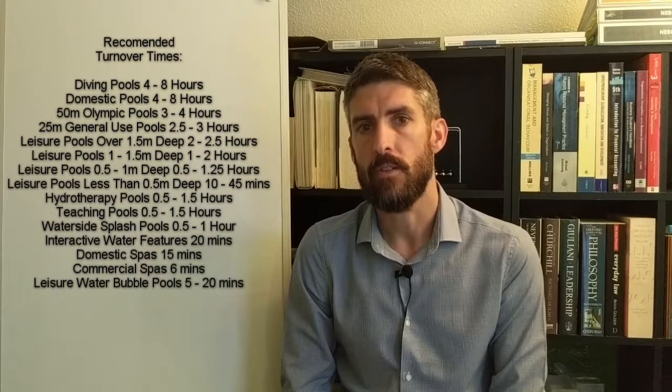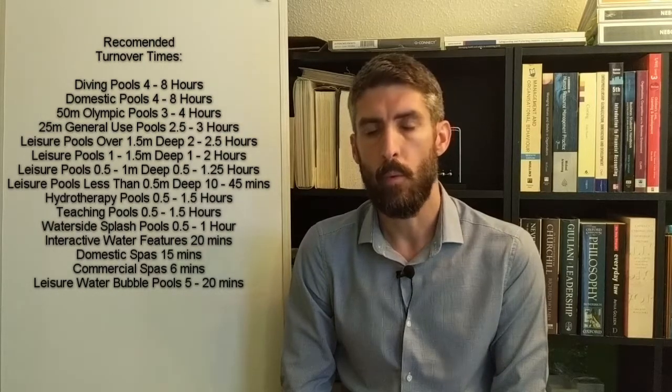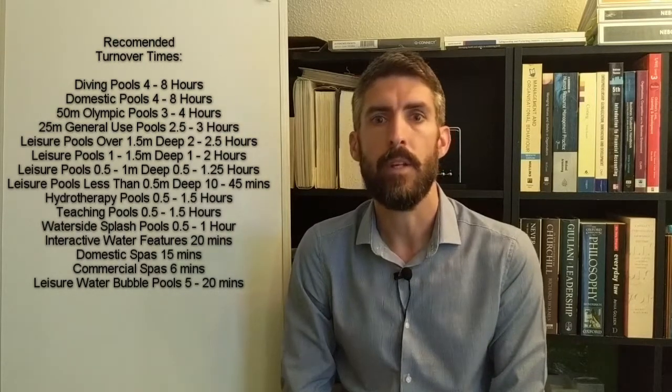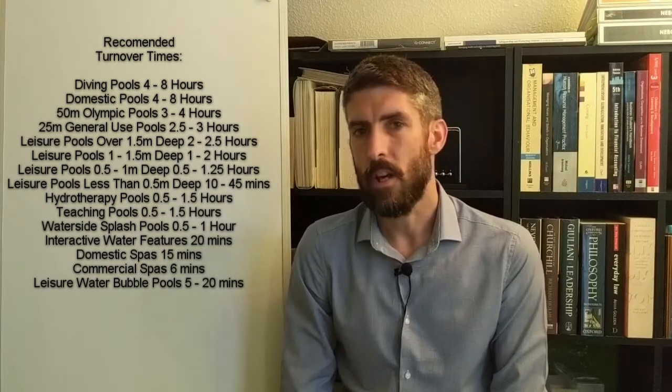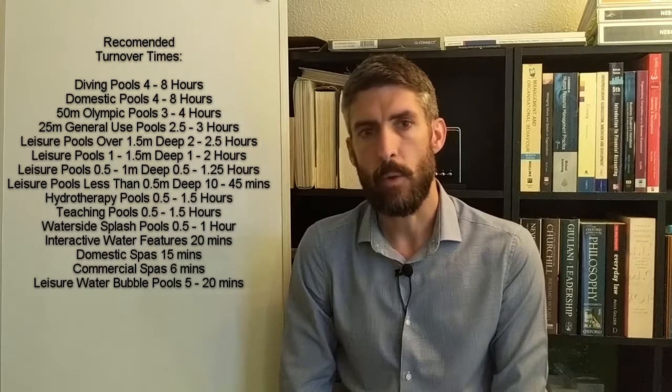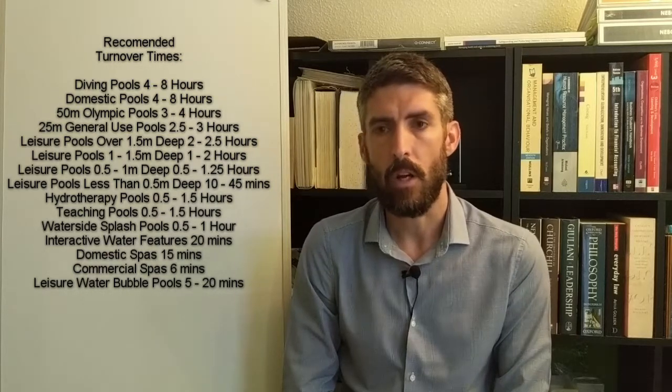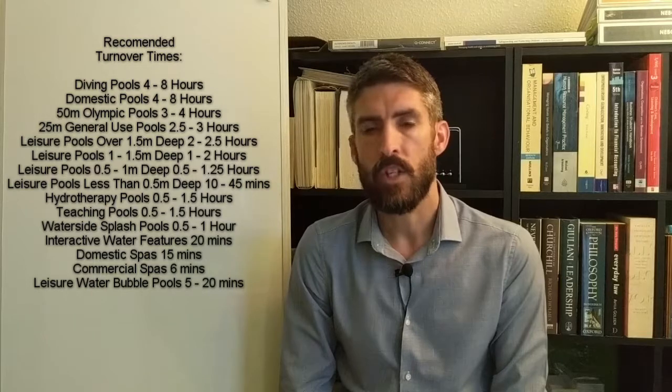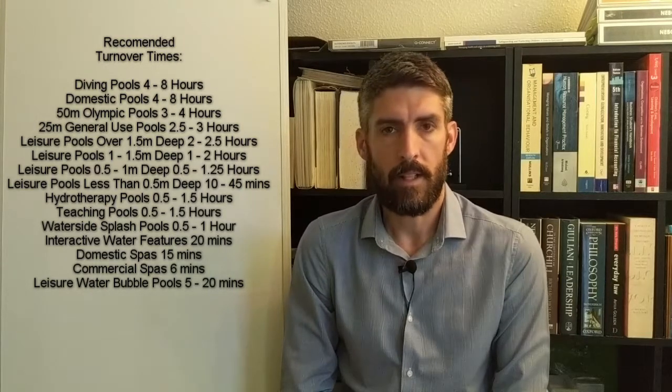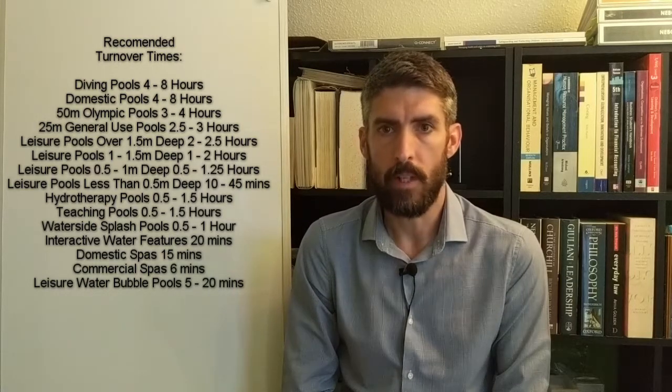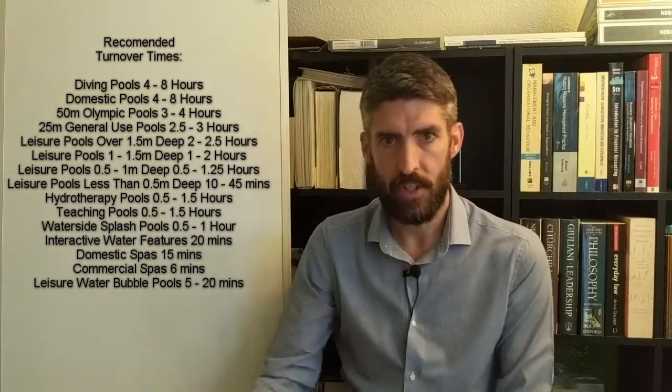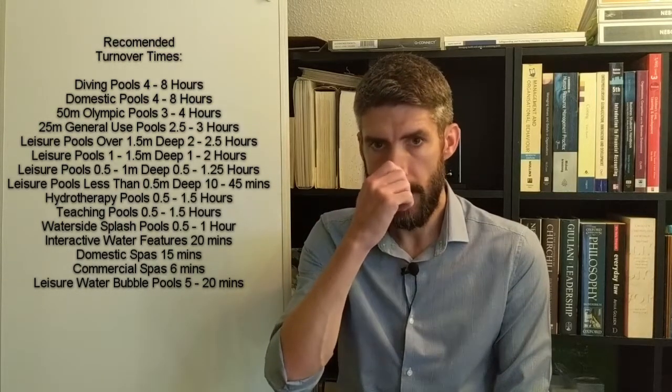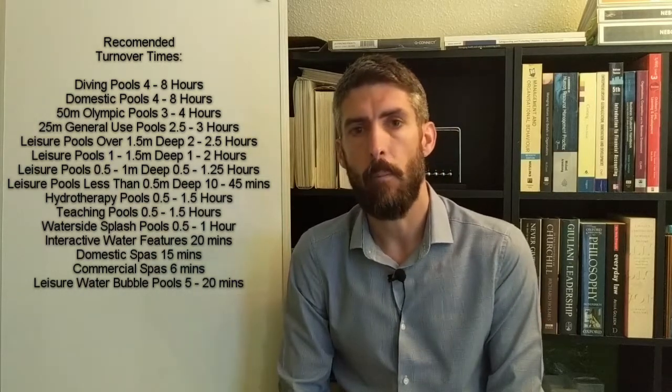For example, a spa pool where the water gets very heavily polluted - high levels of relative pollution - the recommended turnover time is anything between five and fifteen minutes, so very quick. That stands to reason because that water in the spa pool is very polluted. You've got to get that water around the system pretty quickly in order to keep that spa pool water safe, clean and hygienic.